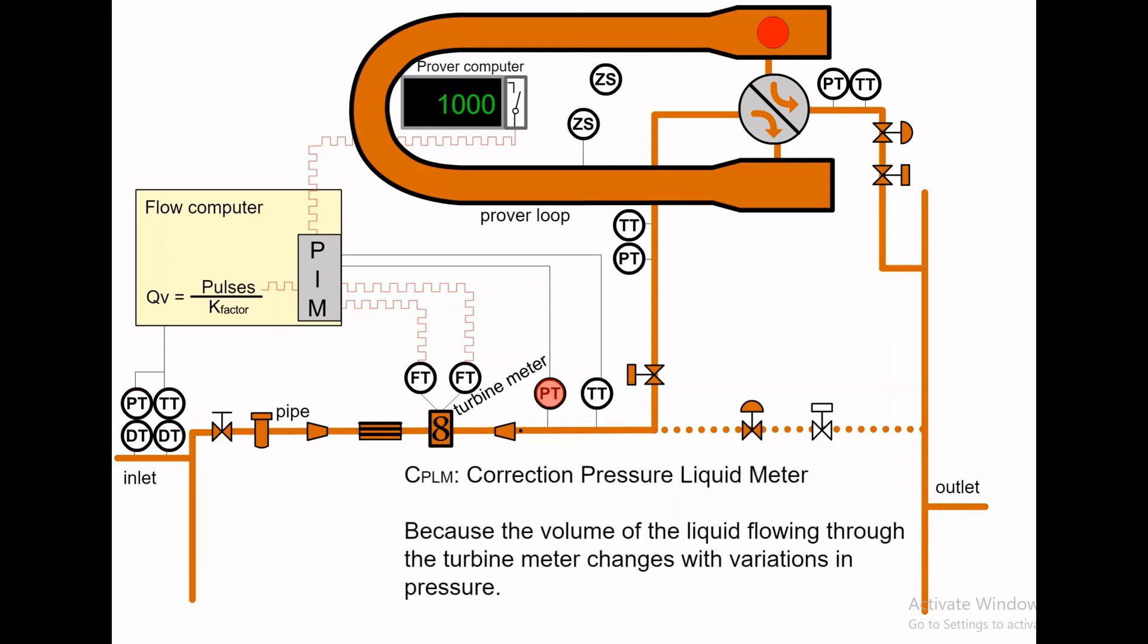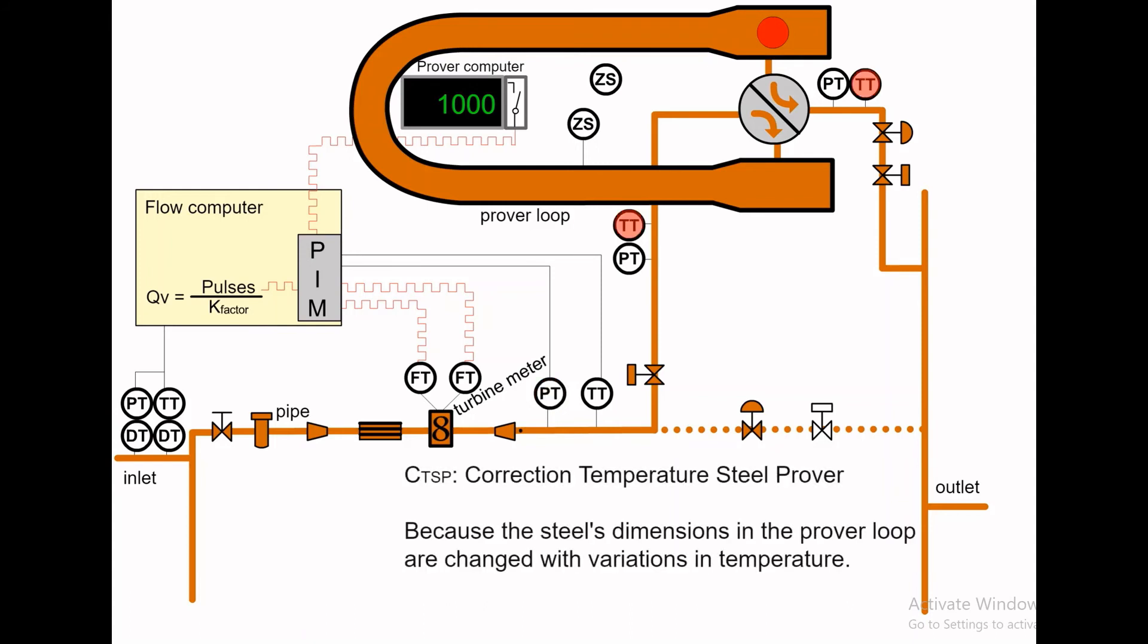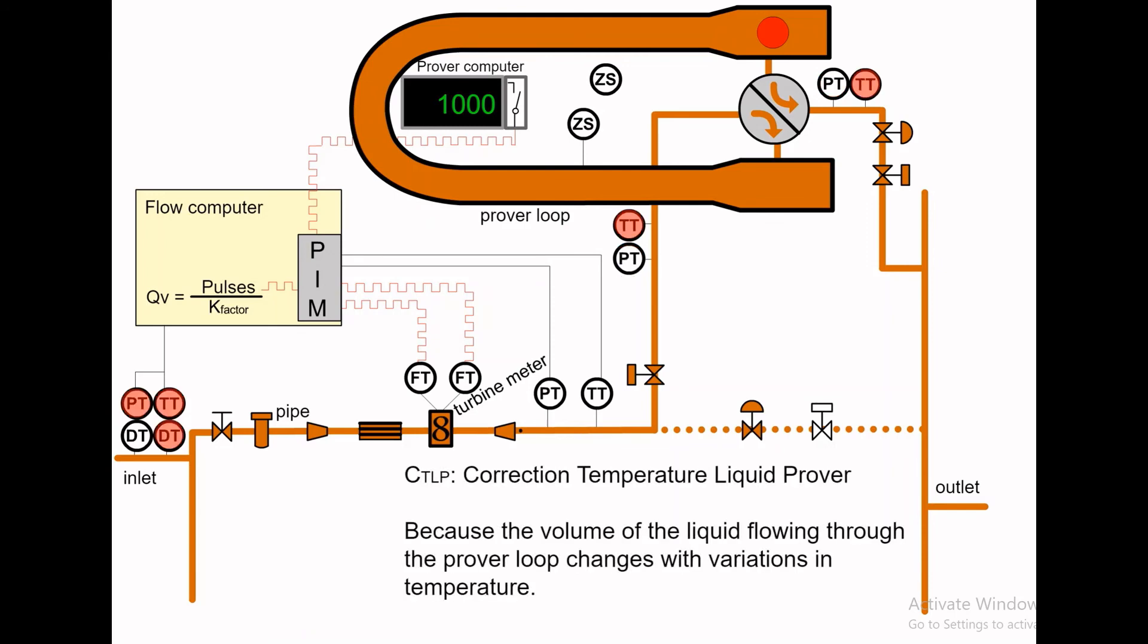CTSP, Correction Temperature Steel Prover, makes the correction required because the steel's dimensions in the prover loop are changed with variations in temperature. CPSP, Correction Pressure Steel Prover, makes the correction required because the steel's dimensions in the prover loop are changed with variations in pressure.